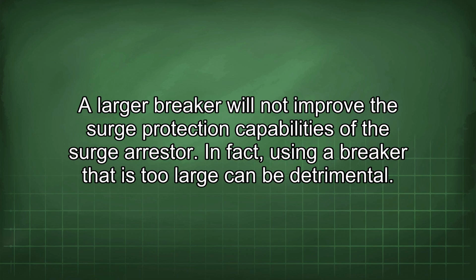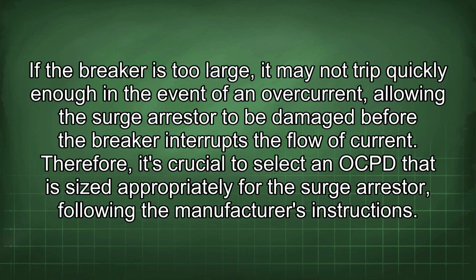In fact, using a breaker that is too large can be detrimental. If the breaker is too large, it may not trip quickly enough in the event of an overcurrent, allowing the surge arrestor to be damaged before the breaker interrupts the flow of current. Therefore, it's crucial to select an OCPD that is sized appropriately for the surge arrestor, following the manufacturer's instructions.